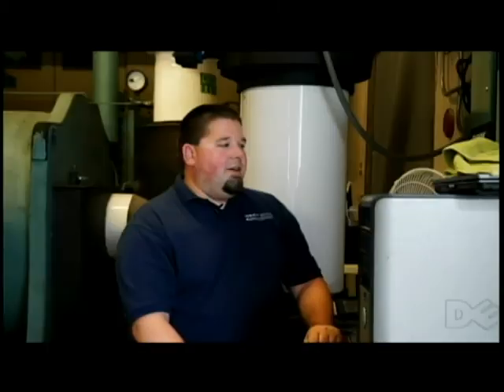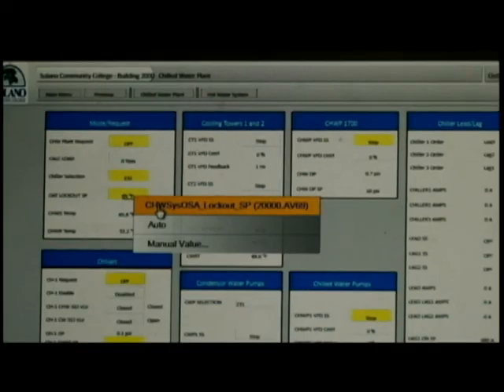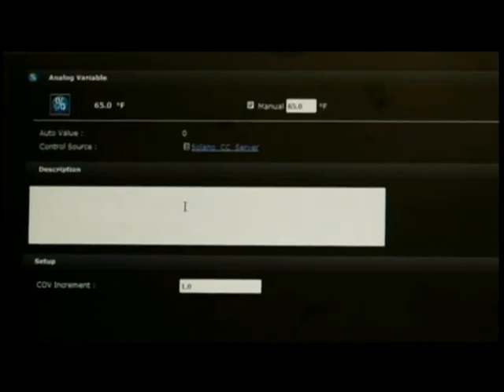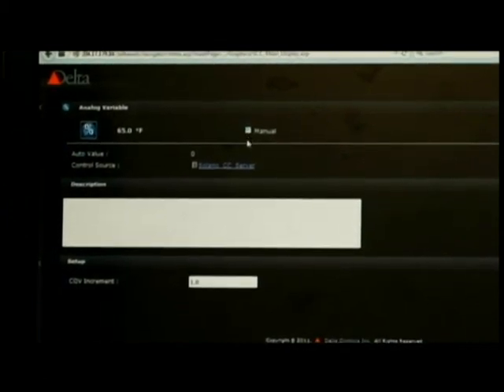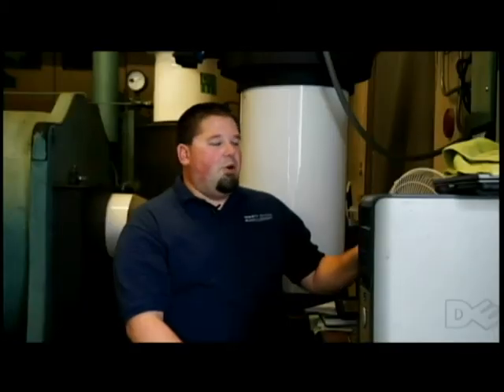That one will actually open up a separate dialog window just for that point, so you can see information about it. So if you select that one, it brings you inside to this point. And once again, you can do this with any points, whether it's inputs, set points, outputs. Inside of here, you can see we're in a manual control because that little checkbox is checked. If you came in here and that was not checked, then that assumes we're in auto control, which allows the programming to dictate whatever that number is going to be.